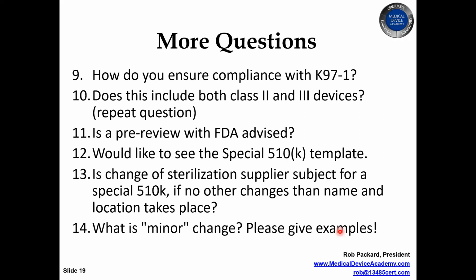Number 11, is a pre-review with the FDA advised? Absolutely. A year and a half, 2 years ago, I would have said, you know, if you're a really smart guy like me that's done a bunch of 510Ks, you don't really need a 510K pre-sub, or if there's a guidance document, you don't need it. And I've retracted those words multiple times. I've learned my lesson. I always do a pre-sub unless the client refuses. So yes, do a pre-sub.